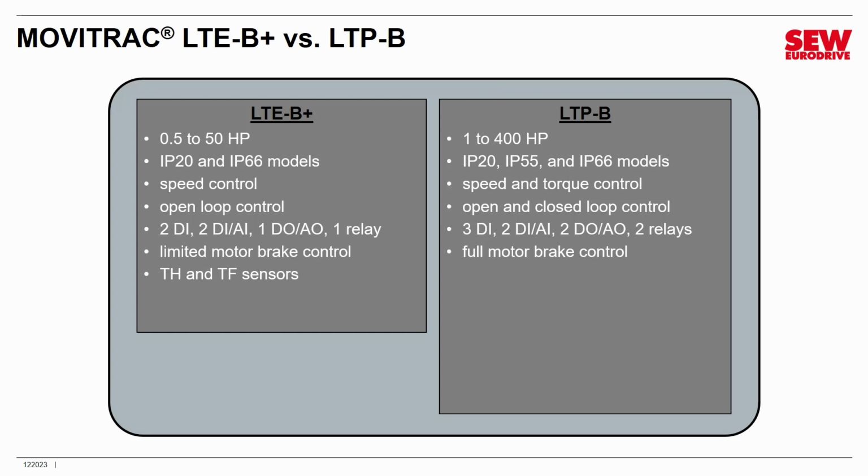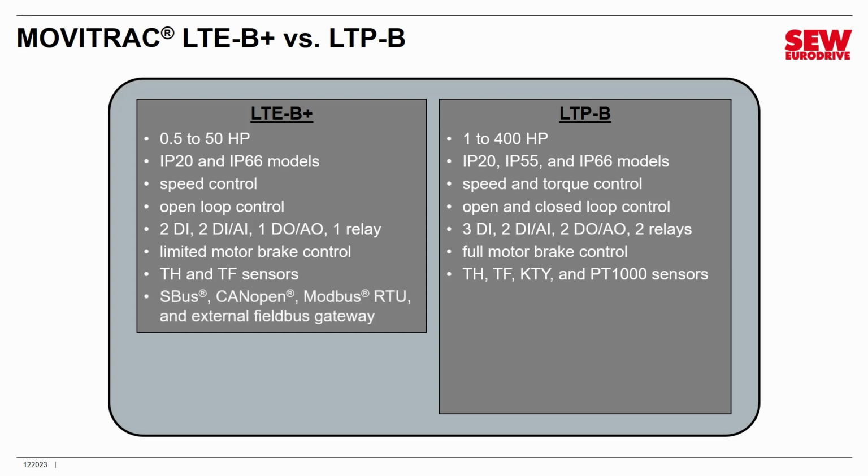The LTE can deal with two kinds of motor thermal protective sensors, thermistors and thermostats. The LTP can use those, but it can also work with advanced thermistors, the KTY and PT1000 sensors. The LTE does have fieldbus communication.